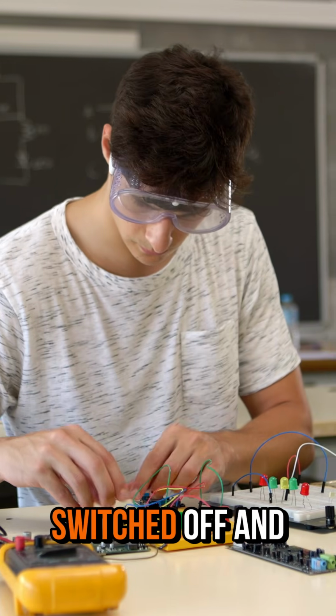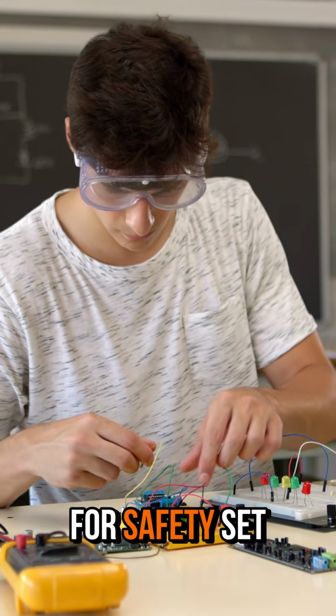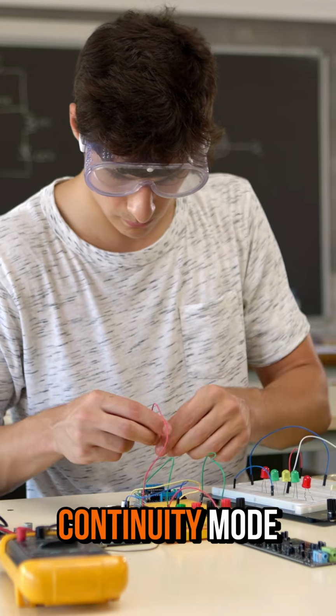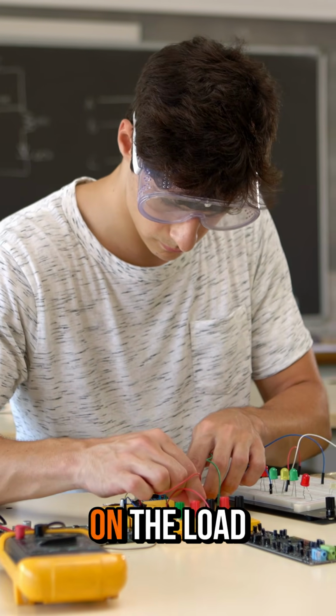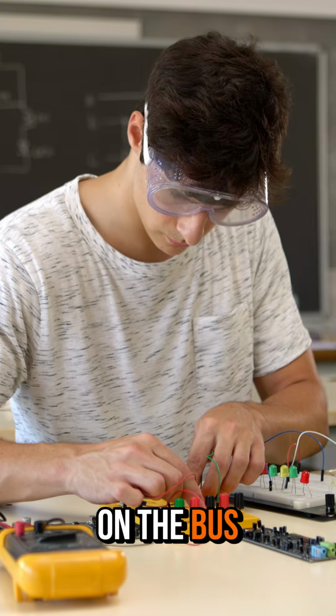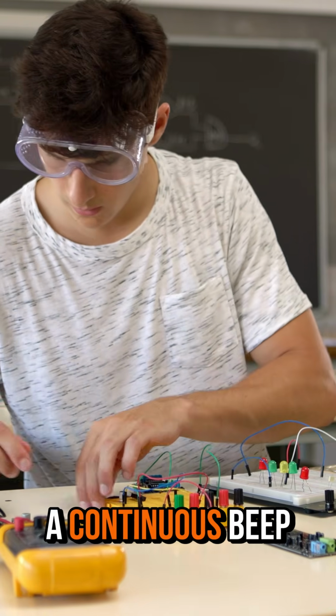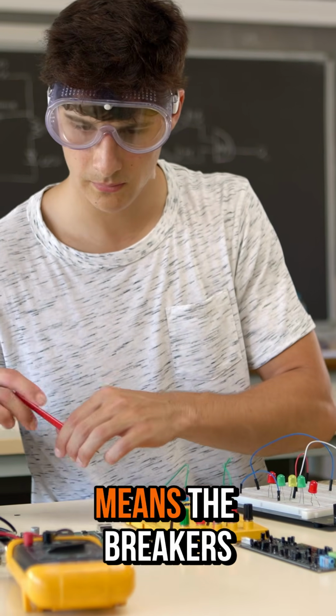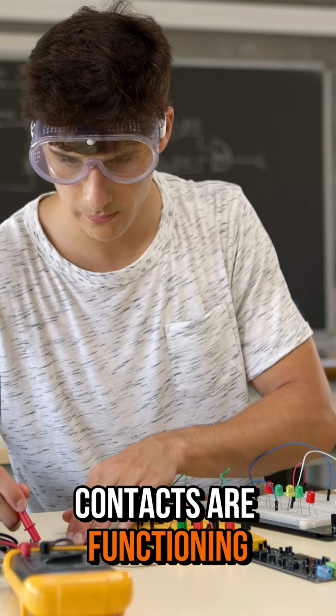With the breaker switched off and the main power off for safety, set your multimeter to continuity mode. Place one probe on the load terminal and the other on the bus bar connection point. A continuous beep or low resistance means the breaker's contacts are functioning properly.